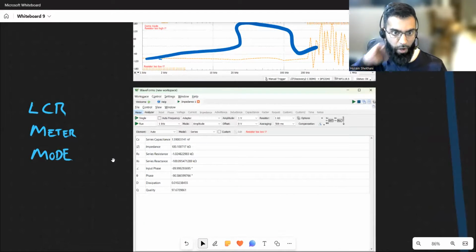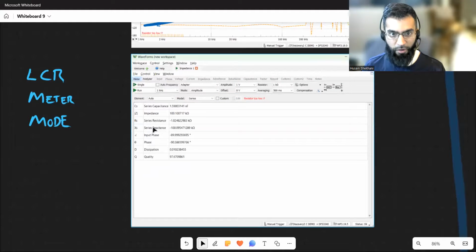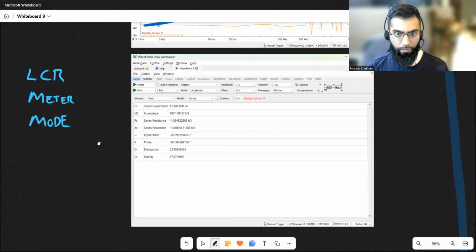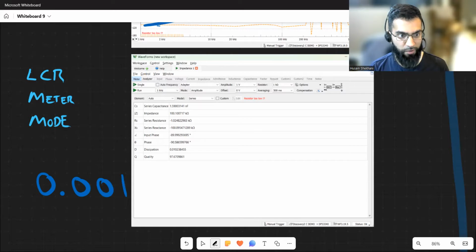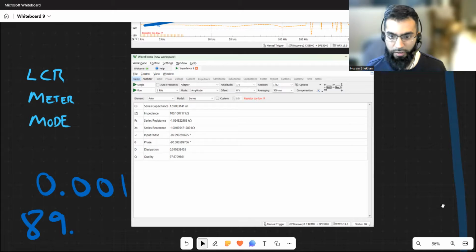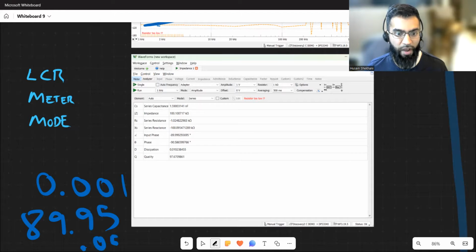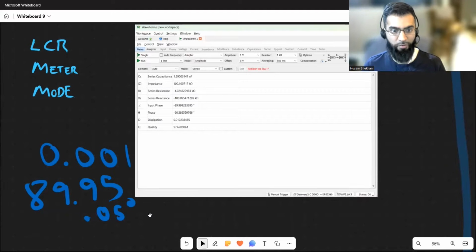You also have the LCR meter mode, which is the only limitation of this device. It can measure your capacitance very well, but the problem, and I'll get into it at the very end, is that it doesn't measure very small phase angles. I'll show you what kind of problem that might cause, because typically in ultrasonic transducer analysis, we measure capacitance at a lower than resonant frequency, and we want the phase angle to tell us the dielectric loss. For example, in order to resolve a dielectric loss of 0.001, I did the calculation here, we have to measure about 89.95 degrees. So we have to be measuring with a resolution of 0.05 degrees, and obviously to trust that, you have to probably have 0.001 at least. That's very small.